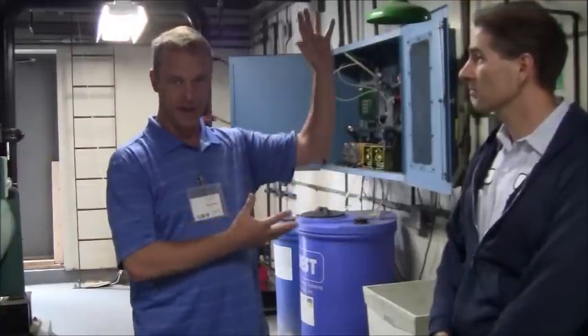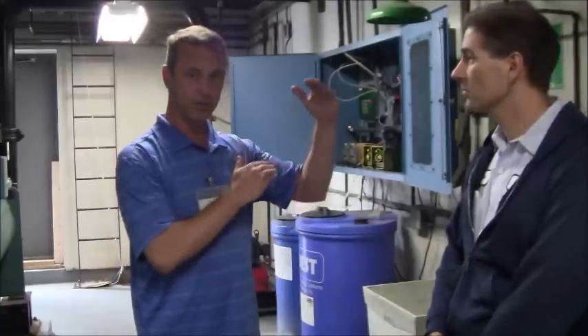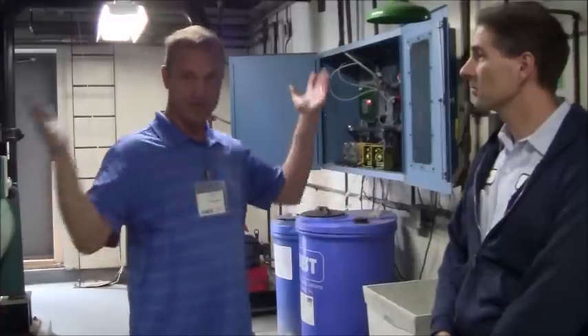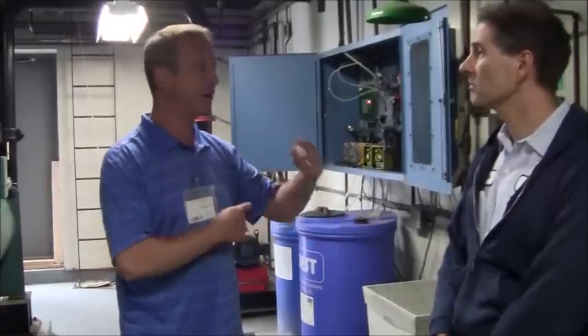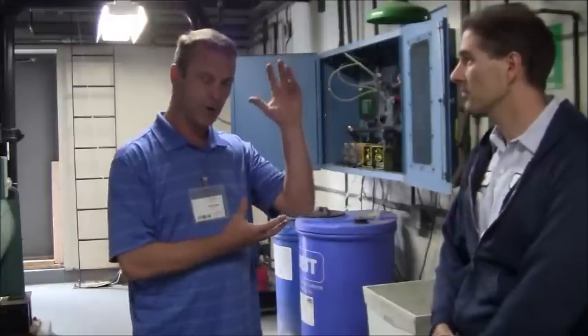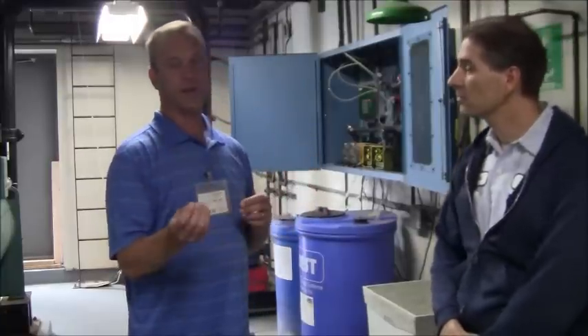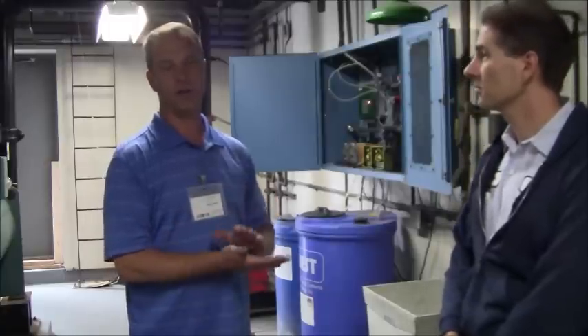But when that water's raining down through the fill, the fan is bringing air across it, and it's releasing latent heat, and that's causing evaporation, which is cooling that water down. We call that a delta T, a split between the temperatures. And that goes back to the chiller barrel, picks up the heat, goes back, rains back down, the fans evaporate the water, and on and on all day long. And what happens when you evaporate this water, the minerals that I spoke of earlier, your calcium, your alkalinity, your impurities, begin to pile up in the tower.